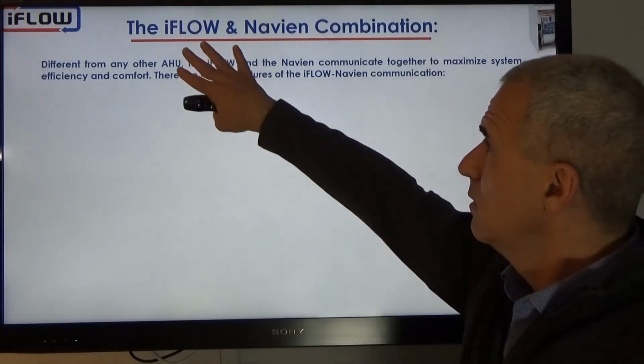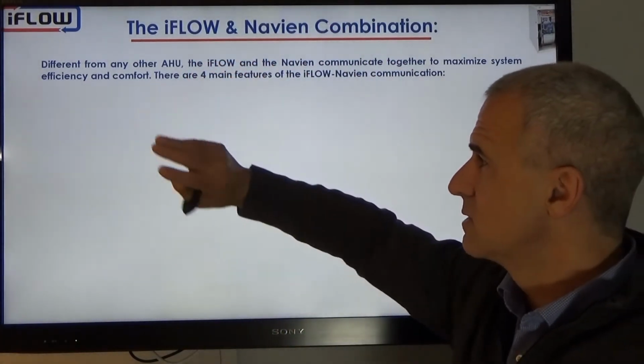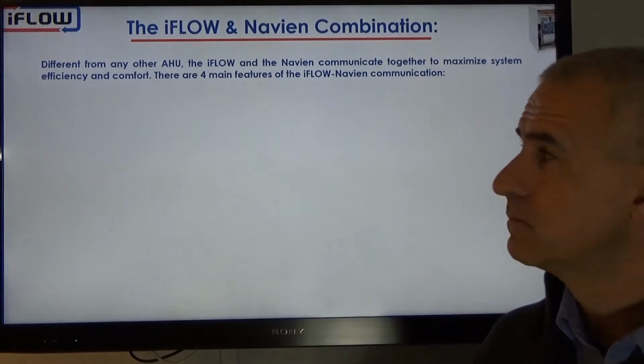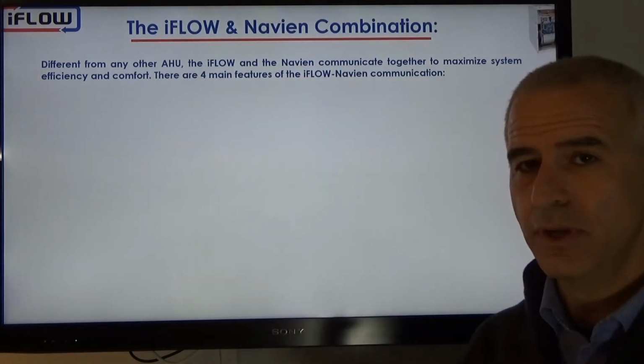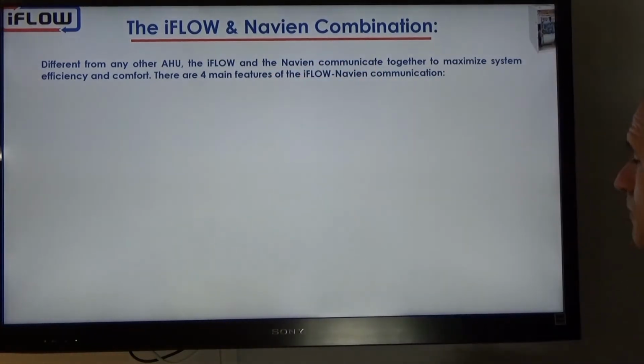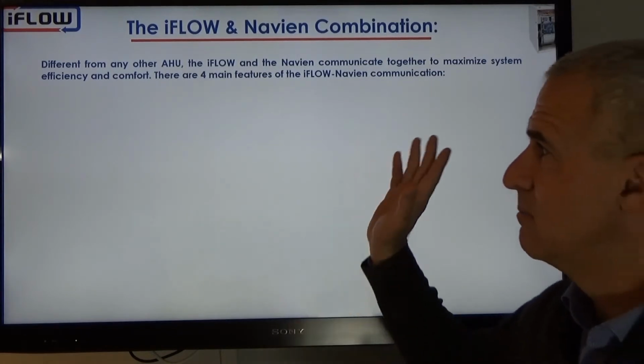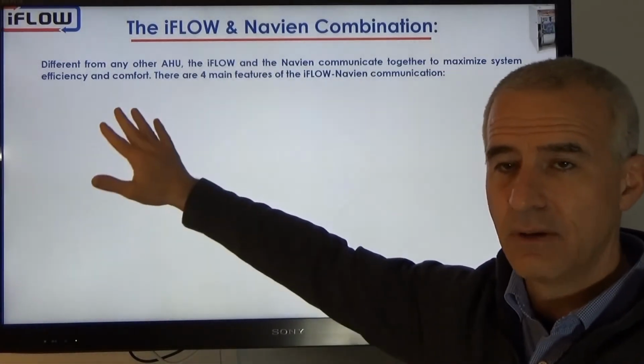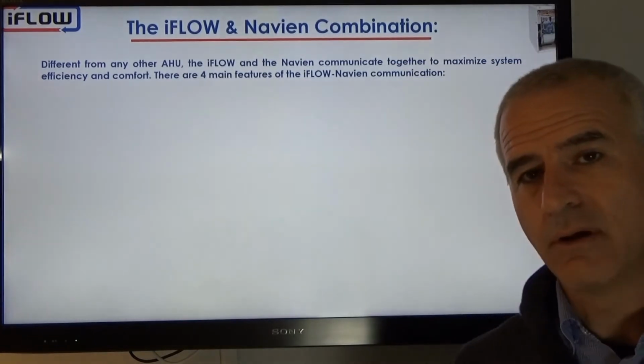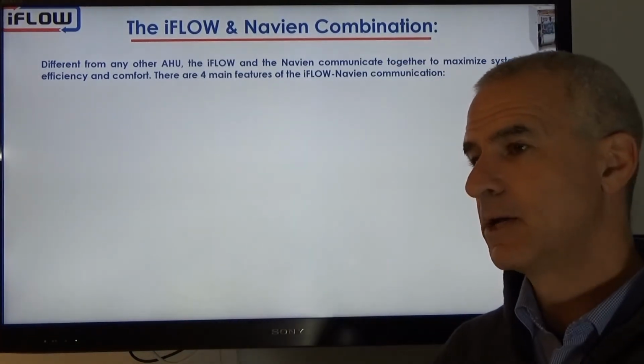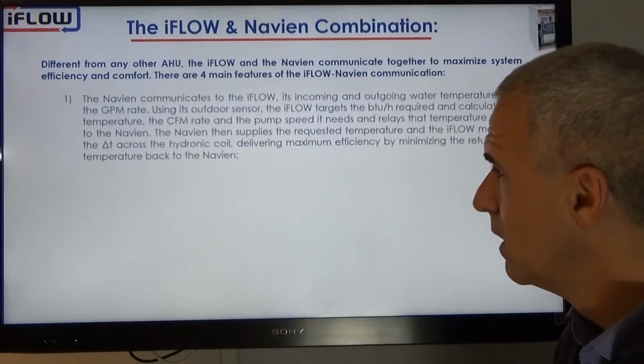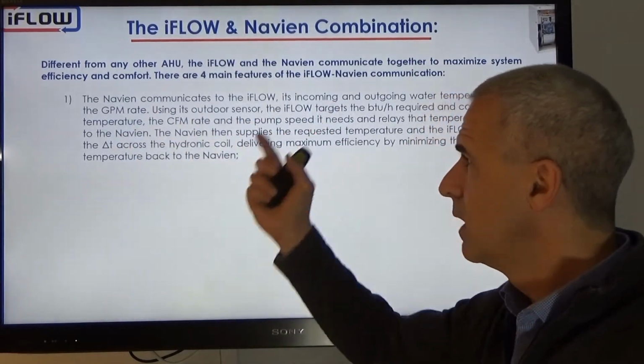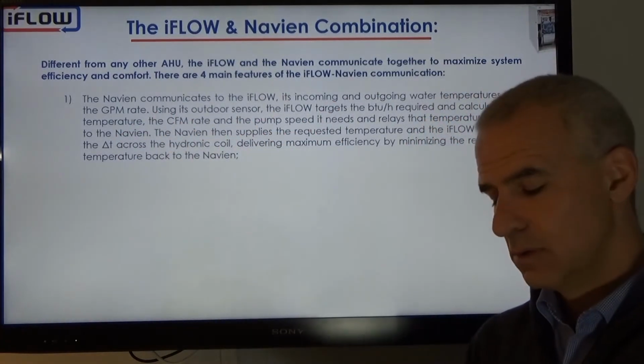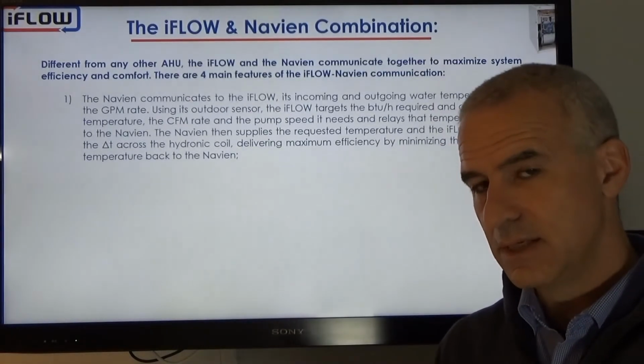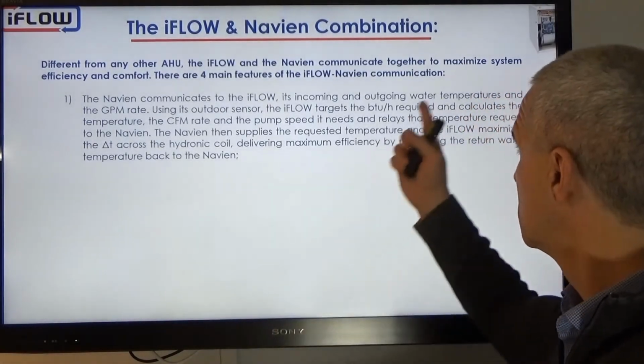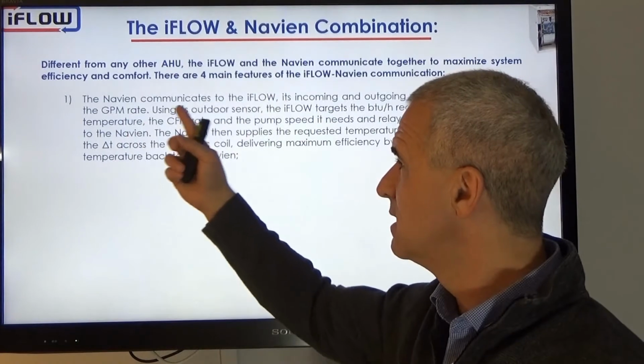So let's look at the Navien iFLOW combination. Different from any other air handler, right? The iFLOW and the Navien can communicate together. We communicate together to maximize the efficiency and the comfort for the homeowners. So really there are 4 ways that we communicate together. Number 1, the Navien will relay to the iFLOW the inlet temperature, the outlet temperature, and the GPM rate, right? So that's coming from the Navien to the iFLOW.